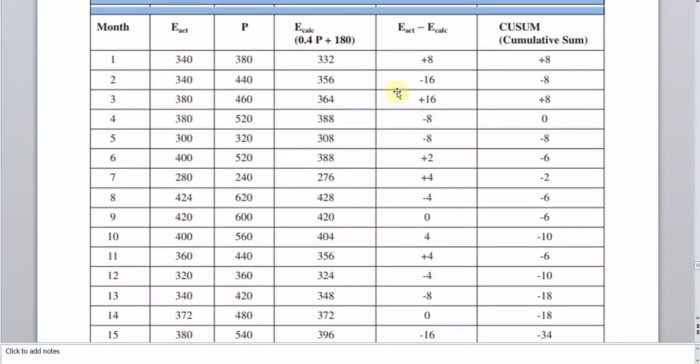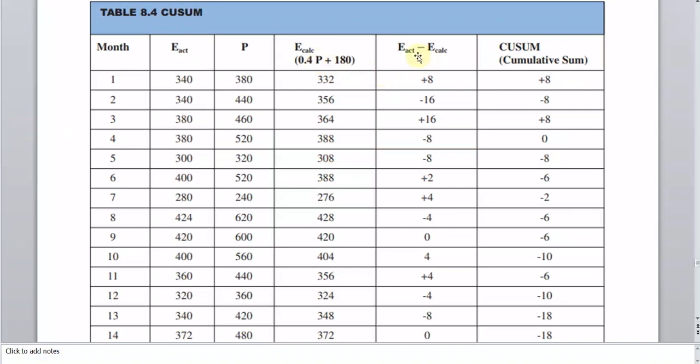After that, we have to calculate the difference between the actual energy consumption and the expected energy consumption. This is nothing but the CUSUM. And after that we have to find the cumulative sum of the CUSUM points.